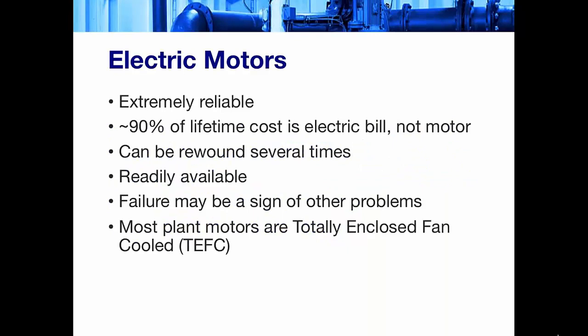Electric motors drive most all of the processes and pumps within water and wastewater distribution systems. They are kind of an incredible advance. When they first came out, they are extremely reliable. If you take one takeaway from today, this next bullet point, that about 90% of the lifetime cost of an electric motor is the electric bill and not the acquisition of the motor itself. There can be some pretty strong business cases for when you replace a motor that it should be efficient. Electric motors can also be rewound several times at motor shops, which basically that's kind of like a pump overhaul equivalent for an electric motor.